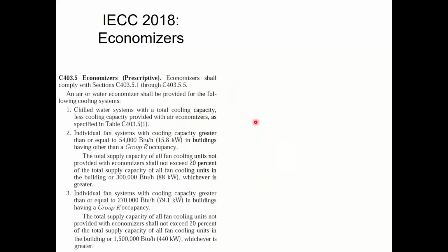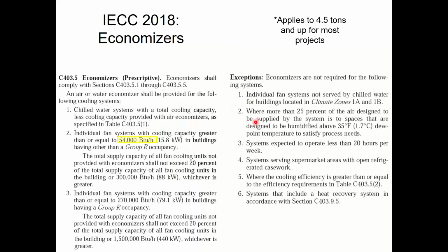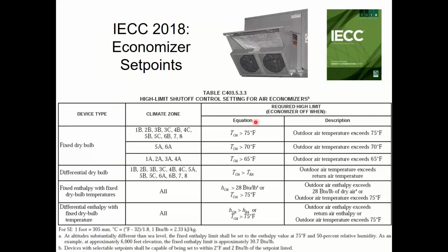So I set it for 57, 58, 59, 60, 62, 65. Whoa, time out. 65 was a problem. 65 didn't work. I would get calls saying it's too humid in there. But 62 and less, I was good. Never had a call back on 62. So I just set every job at 62 instead of his 55. And at 7 more degrees of outside air, which is several hundred hours per year for most climate zones, I got free economizer cooling.